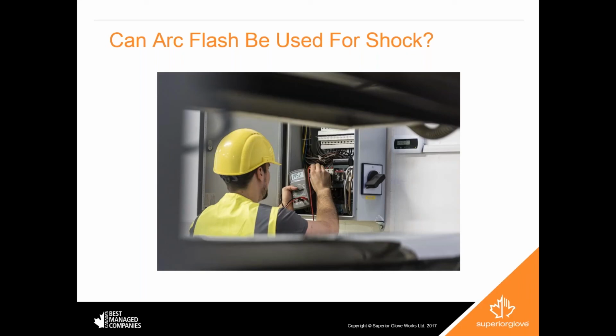But basically, under NFPA 70E, the 2015 edition, there are 4 categories. Category 1 would be a minimum arc rating of 4 calories per centimeter squared. Level 2 would be 8 calories per centimeter squared. Level 3 would be 25 calories per centimeter squared as your minimum PPE rating. And category 4 would be 40 calories per centimeter squared. And again, you can find all of those in the NFPA 70E standard.